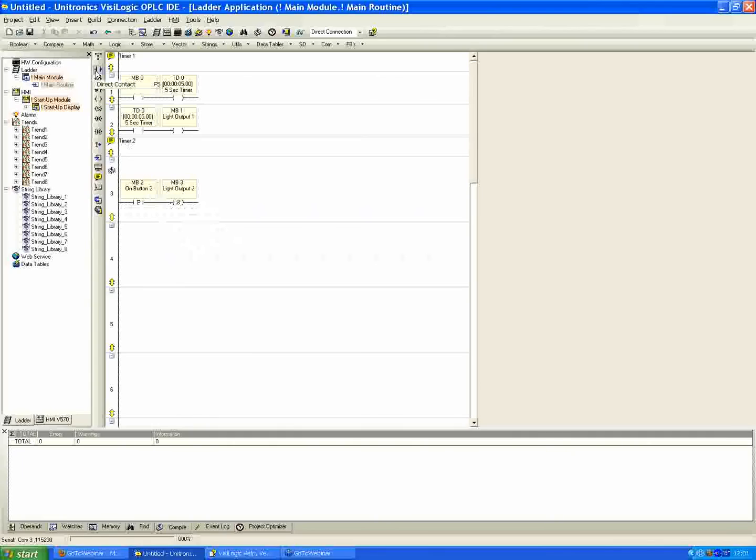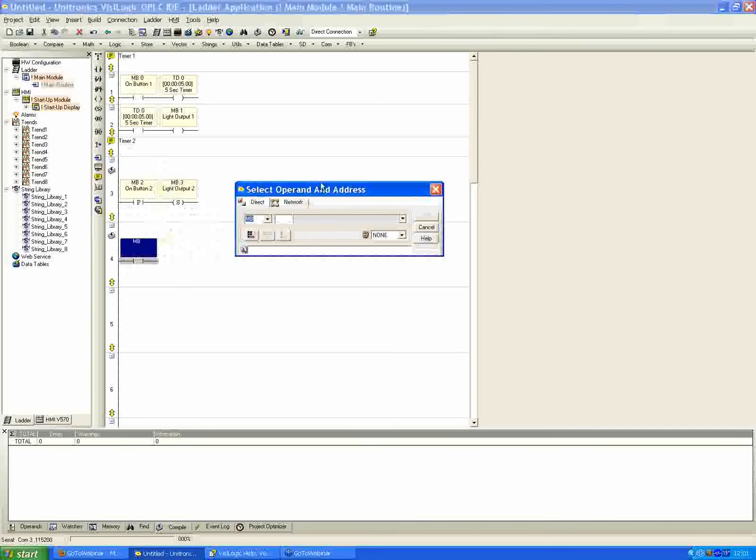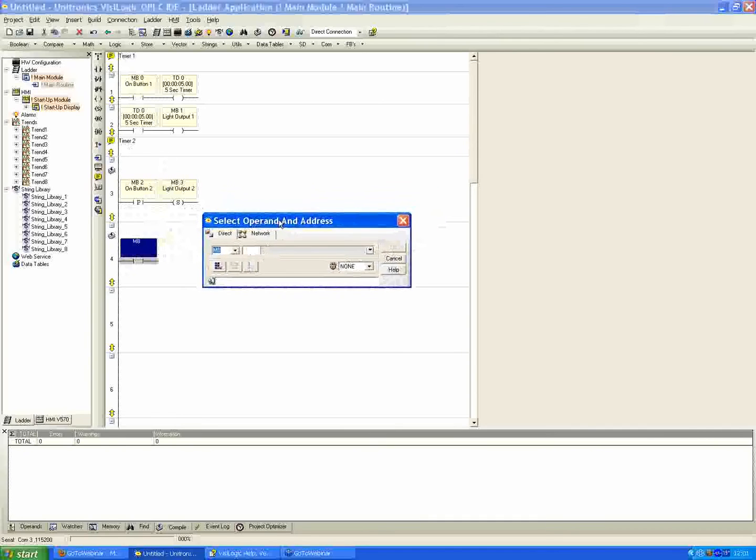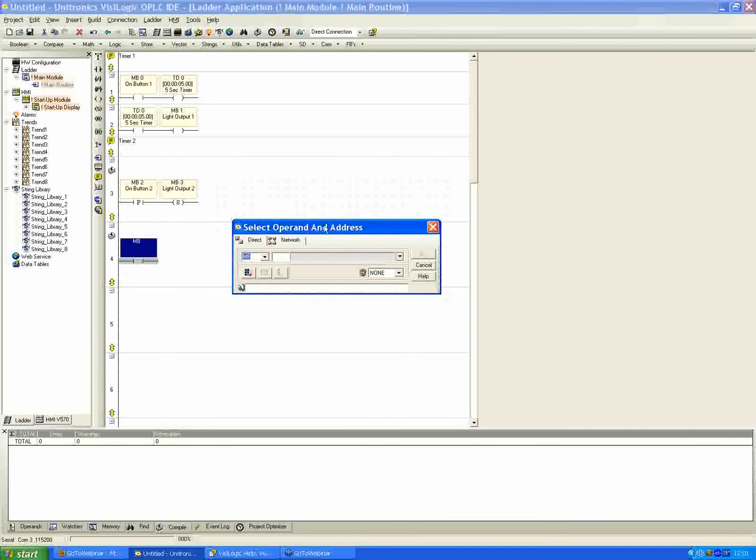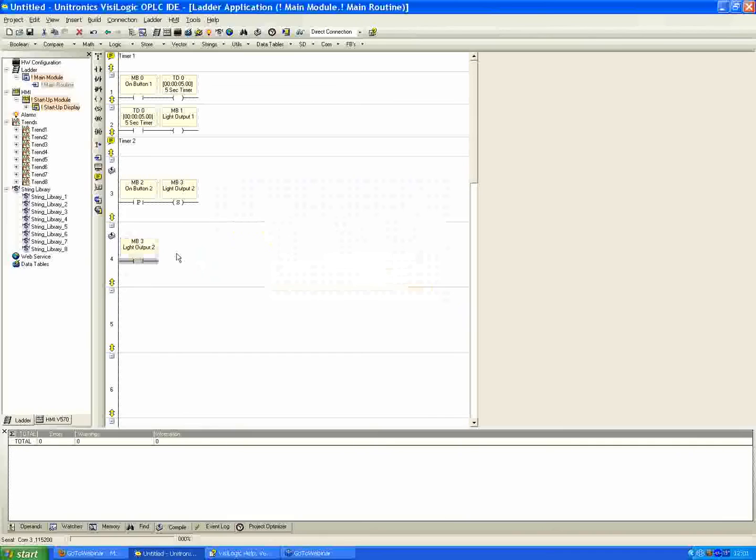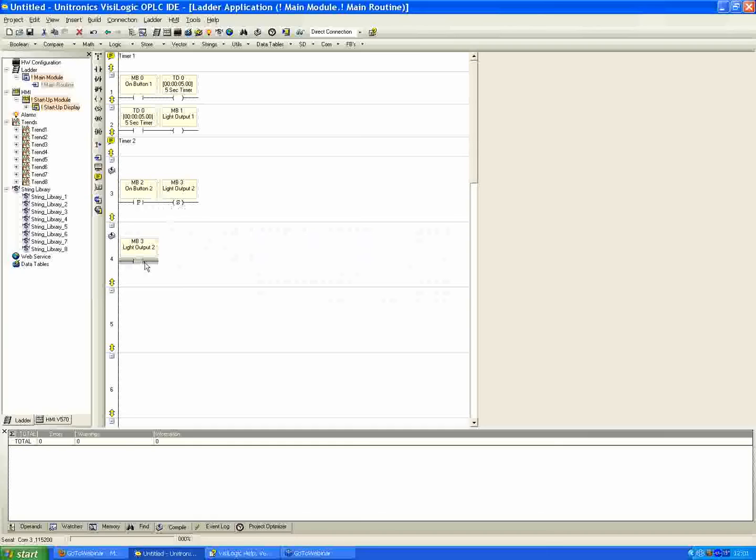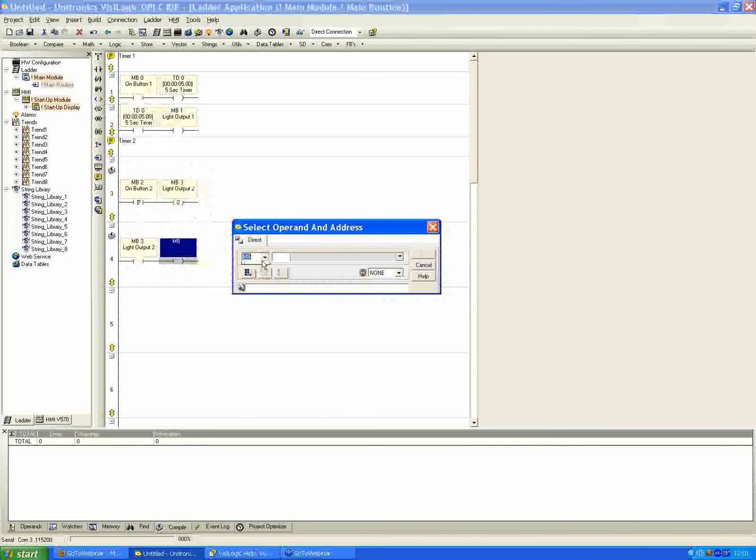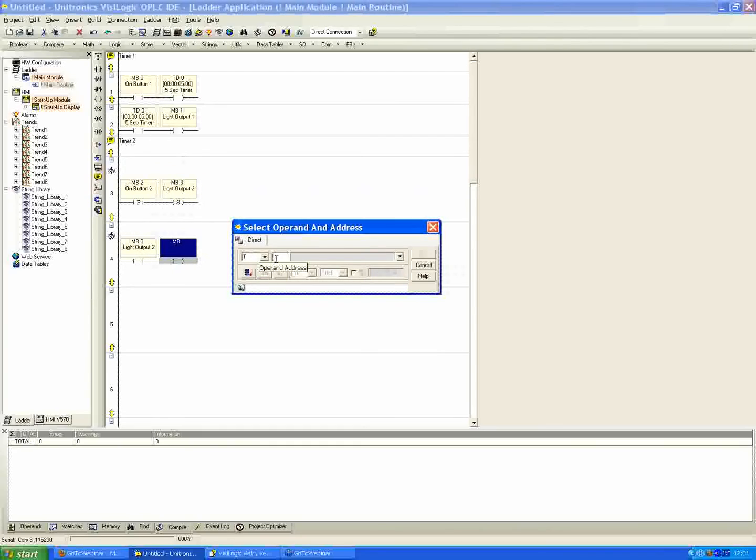So we have our button we're going to press, we're going to set our light output. So the next element is going to be a direct contact, which will be placed in the net right below. So we still need some constant condition to energize our timer for it to count down. So the way we're going to do that is we're going to use our light output number 2 as the enabling condition to energize the timer number 2 coil. So we're going to push the button, it's going to set the output here which is going to be on, allowing power to flow through MB3 here since it's in the on state. And then the other element we need is a direct coil, which is going to be our timer that's energized by the light output 2. So in this case, our T1, I named it timer 2, which is maybe a little bit confusing.